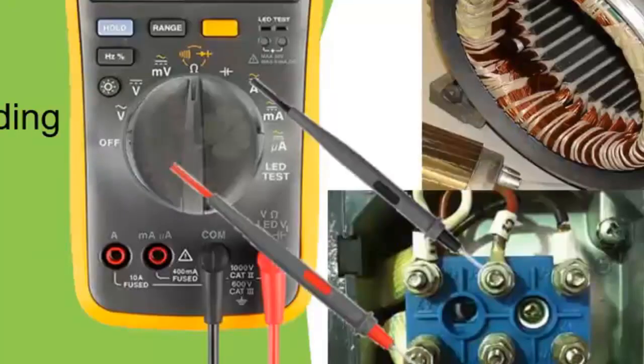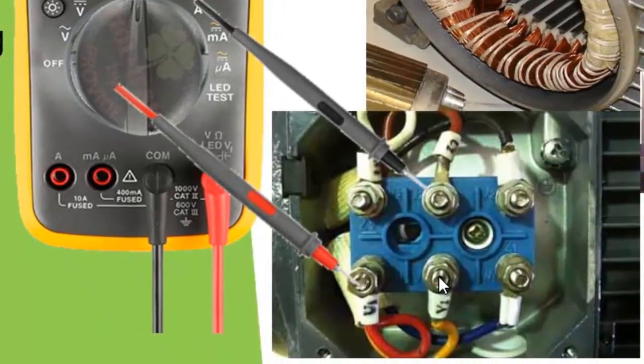Then you will do the same for the V phase, that is between V1 and V2, and finally between W1 and W2. Then you will take U1 to ground to show if it is shorted, then V1 to ground to show if the V phase is shorted to ground, and then W1 to ground. That means one of the probes will be permanently on the frame of the motor. Then you take the red probe to U1 to test if U is grounded, to V1 to test if V is grounded, and to W1 to test if the W phase is grounded. Then the turn to turn short.